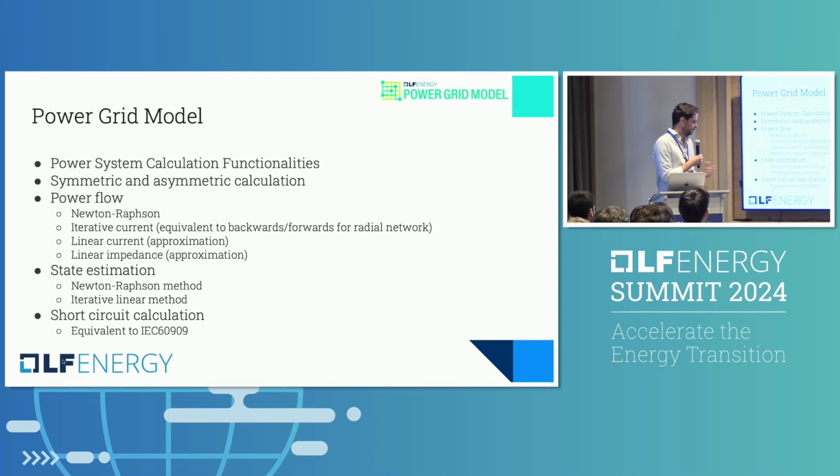For state estimation, we have a Newton-Raphson method and an iterative linear method. And for short circuit calculations, we have a method that's equivalent to the IEC standard, IEC 60909.